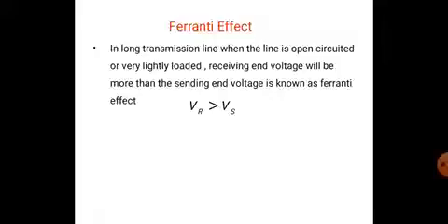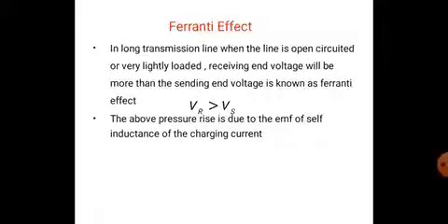Normally we do not see this, but in case of transmission lines, the output voltage will be more than the input voltage. That is, the receiving end voltage is more than the sending end voltage. That is known as Ferranti effect. In a long transmission line, when the line is open circuited or very lightly loaded, the receiving end voltage will be more than the sending end voltage. This is known as Ferranti effect.